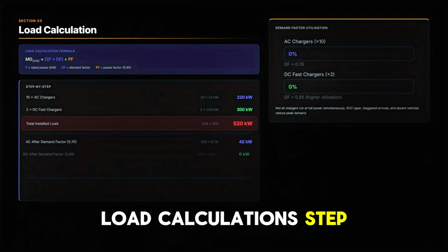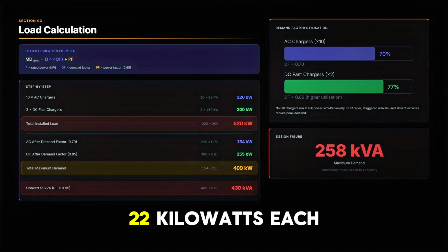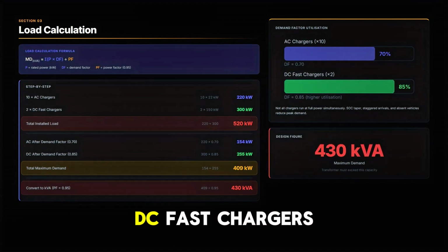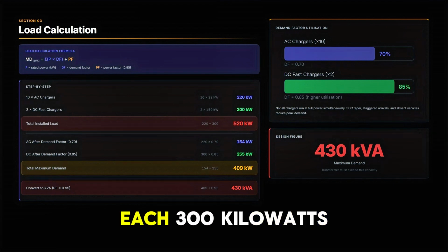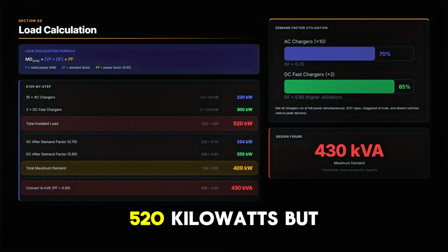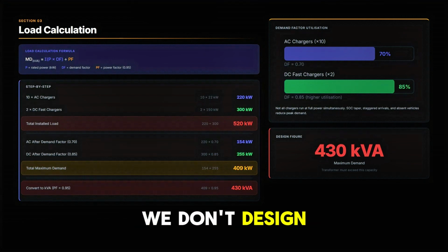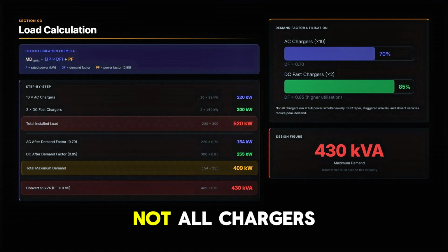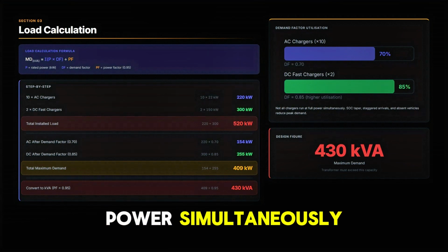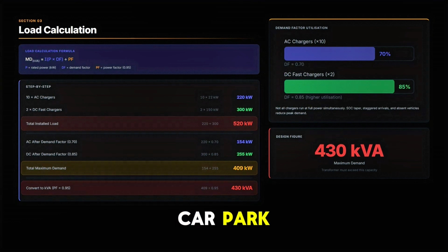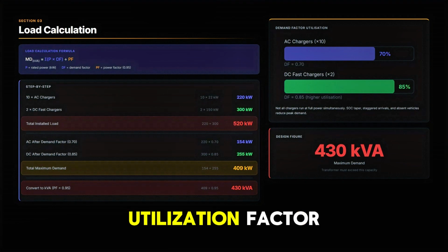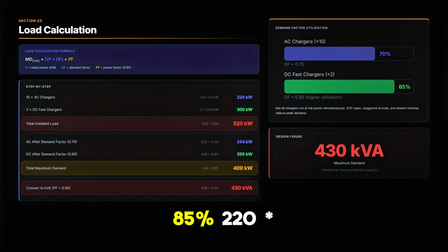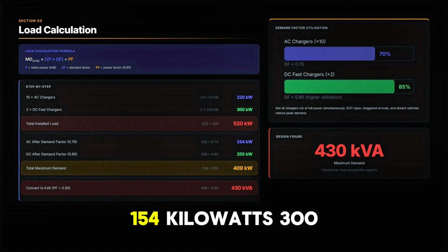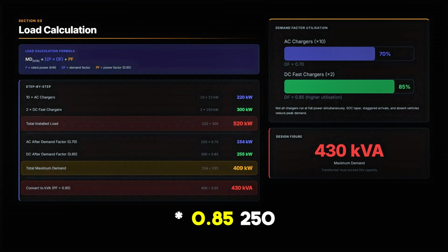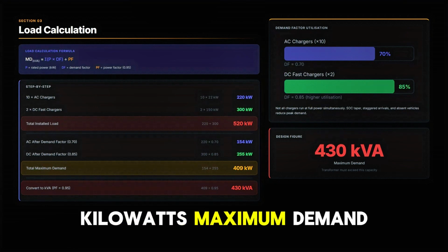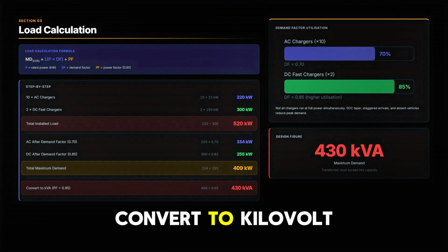Load calculations. Step 1, installed load: 10 AC chargers at 22 kilowatts each, 220 kilowatts, 2 DC fast chargers at 150 kilowatts each, 300 kilowatts, total installed load 520 kilowatts. But we don't design for 520 kilowatts. Not all chargers run at full power simultaneously. We apply demand factors. For a commercial car park, AC chargers, 70% utilization factor, DC fast chargers, 85%. 220 times 0.7, 154 kilowatts, 300 times 0.85, 255 kilowatts. Maximum demand, 409 kilowatts.